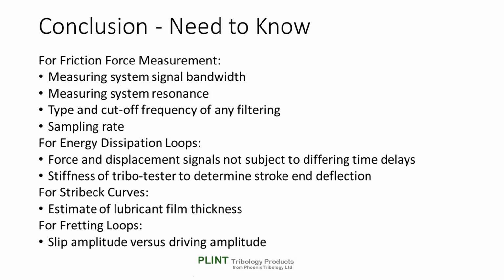And finally, any test standard involving dynamic force measurement should include the requirement to specify the signal bandwidth of the measuring system, the resonant frequency of the measuring system, the type and cutoff frequency of any filtering, and the sampling rate. Or perhaps we should just ask everybody to equip themselves with some string, a pulley, a weight, and a pair of scissors.